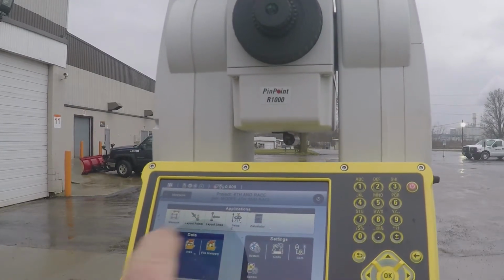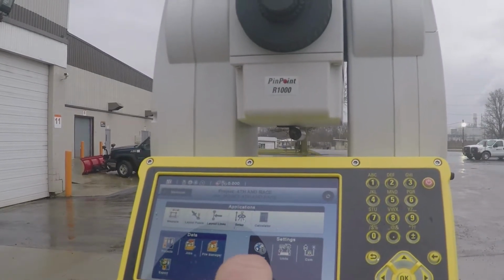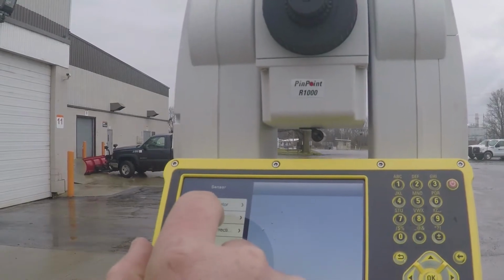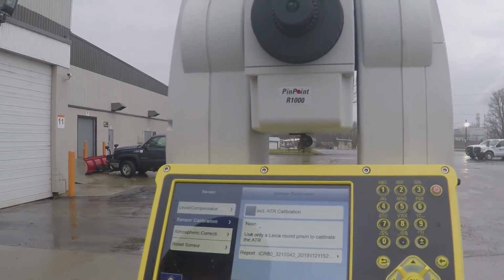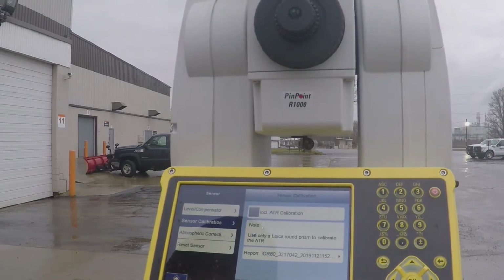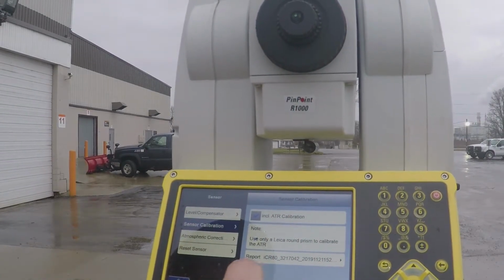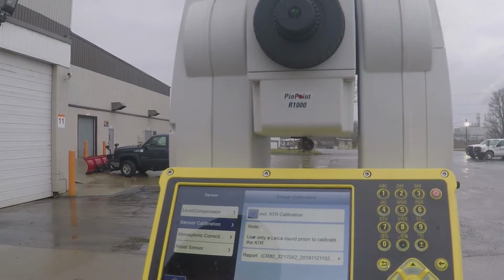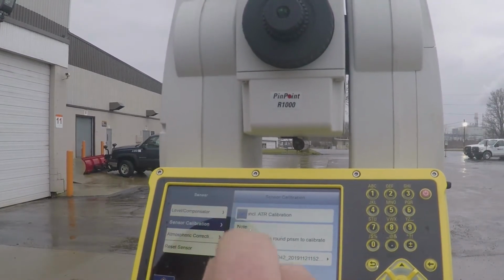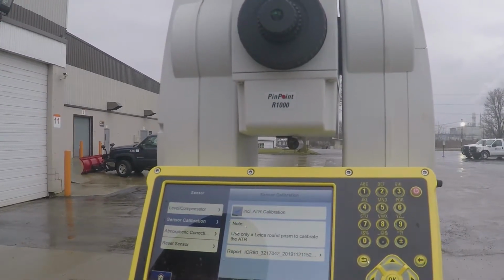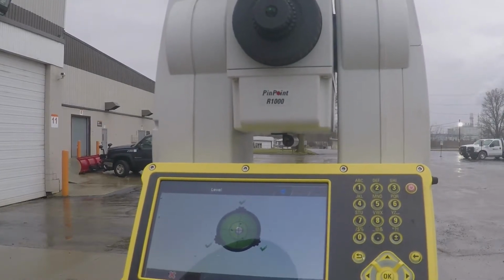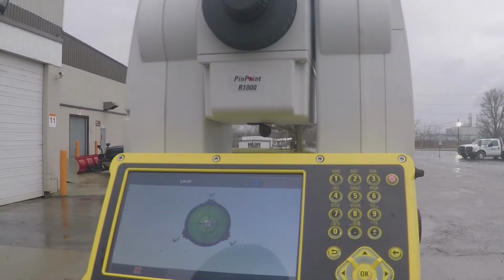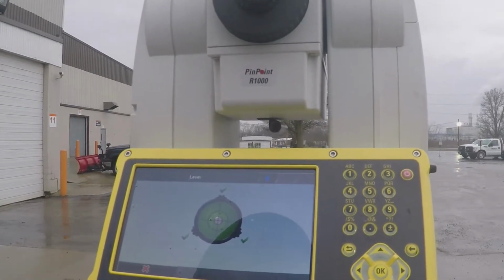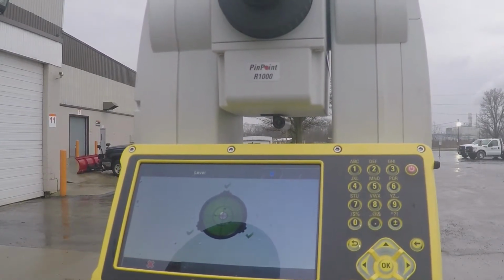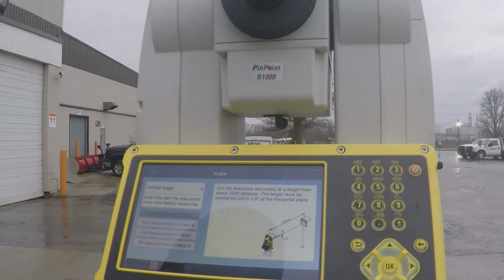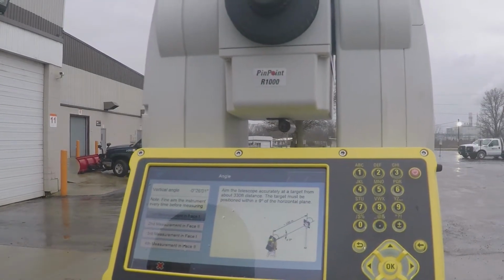So again, from the home screen, we're going to go to the sensor, sensor calibration, and we're going to include the ATR calibration with this. And then right here is basically the report it's going to spit out. So include ATR, green check mark, and it's basically going to the levels screen. So maybe we'll just fine tune it just a hair. Looks pretty close. And then we're going to hit the blue dot to advance to start the calibration.